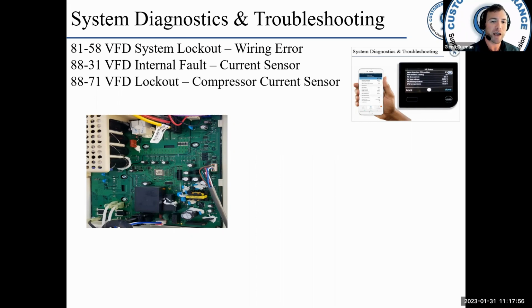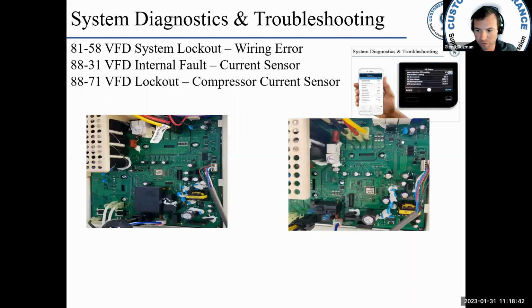But you could also use that fault to your advantage. If I suspect an issue with the VFD, will the VFD determine a wiring error? If I pull the wires off the compressor and try to run the system, I would expect the VFD to correctly identify a wiring error. If it doesn't, that could help me in determining if I have a problem with the VFD. If I'm at that situation, where it's a VFD or maybe it's something else, let me cause this fault by disconnecting the compressor. And if it correctly throws the fault, then that might help me in determining what my next step is. So you can use that one to your advantage.